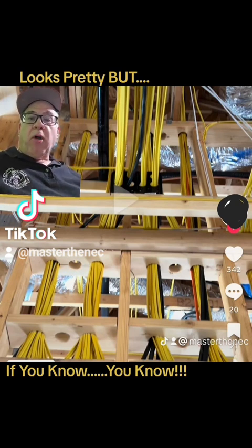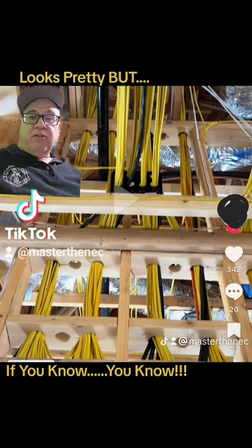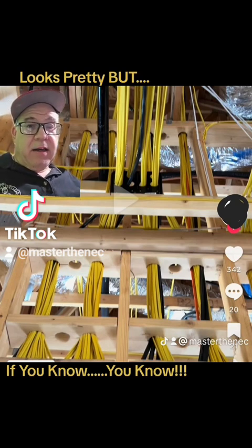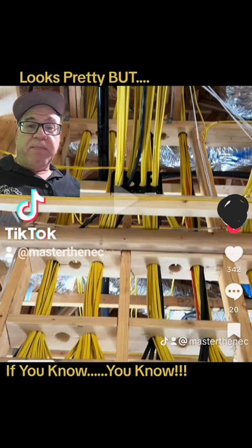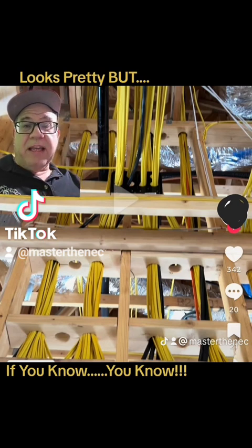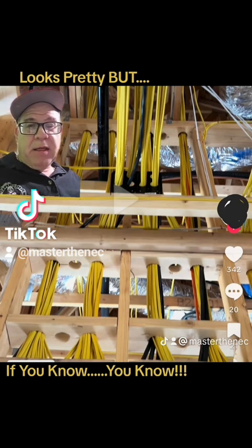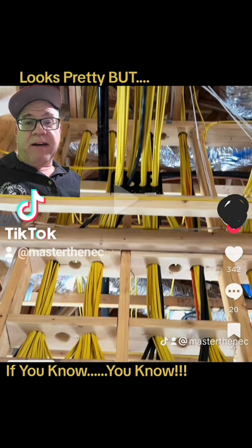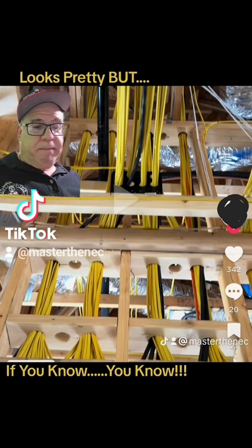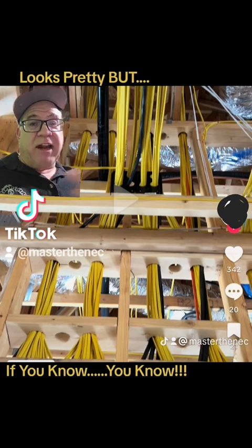A lot of people brought up that I posted a snippet of 310.15(C)(1), which is about maintaining spacing of cable assemblies and when to apply adjustments for more than three current-carrying conductors. In this scenario, everybody throws up the term 'bundling.' We're used to that concept, and we have definitions of 'cable bundle' in Article 100 of the 2023 NEC — though that definition only applies to Article 520. The question is, 310.15(C)(1) doesn't mention the word bundling at all, so that definition is not really germane here.